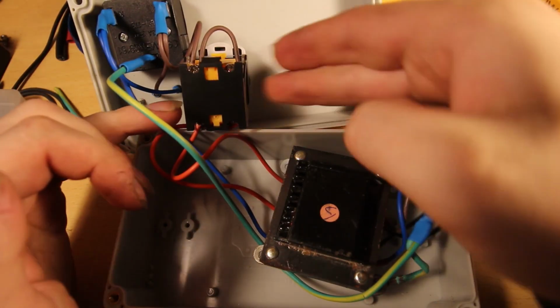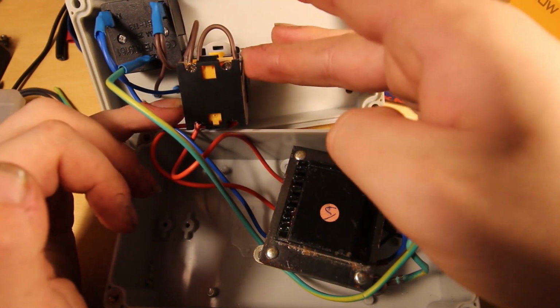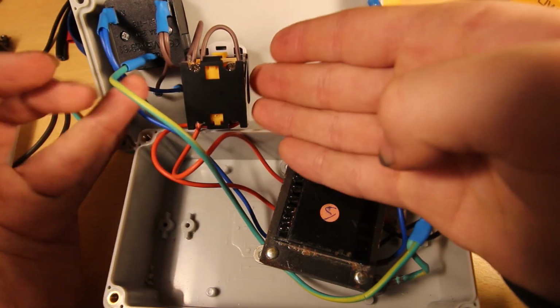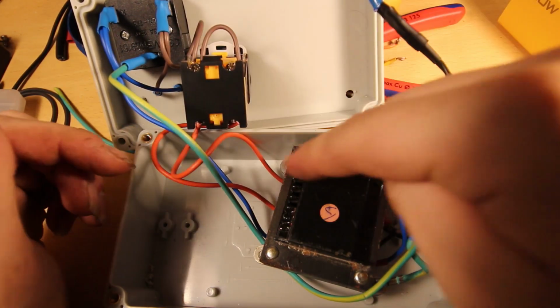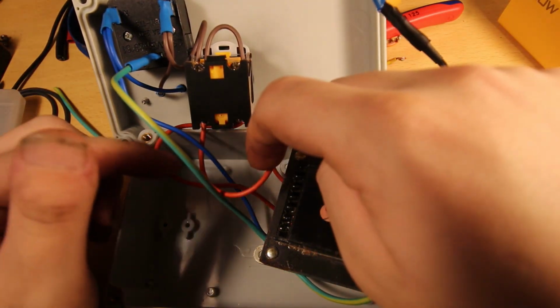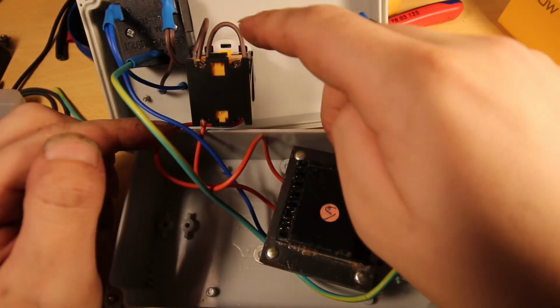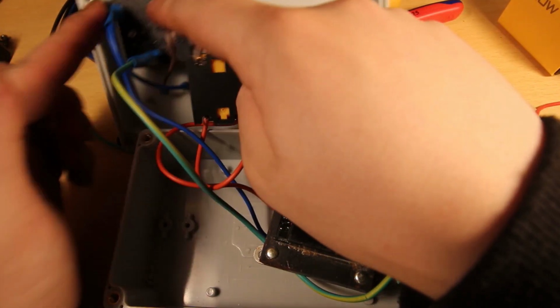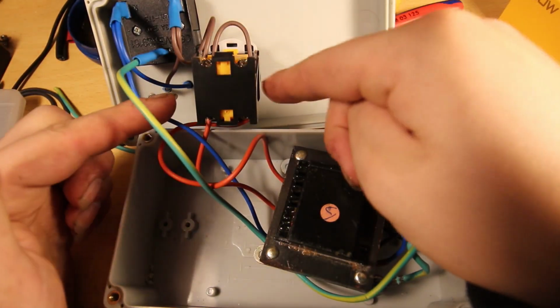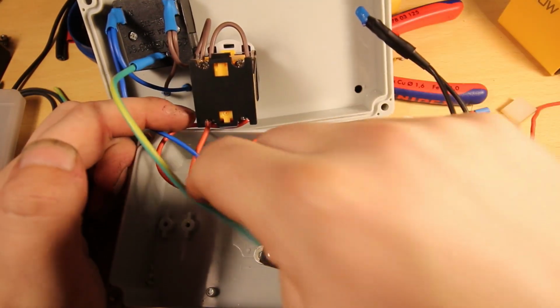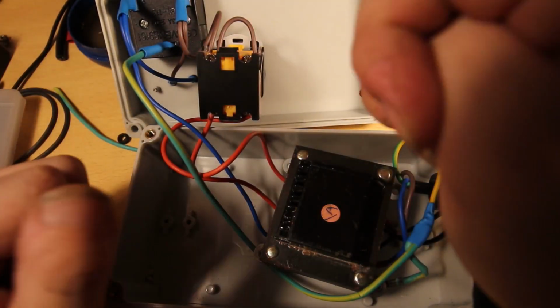Basically, when this is normally closed, power will come from the centre tap through here to here, and we have 115 volts. If you switch the switch, you open this and close that, and you get the other end coming through to here, giving you the full 240 volts out the other side.